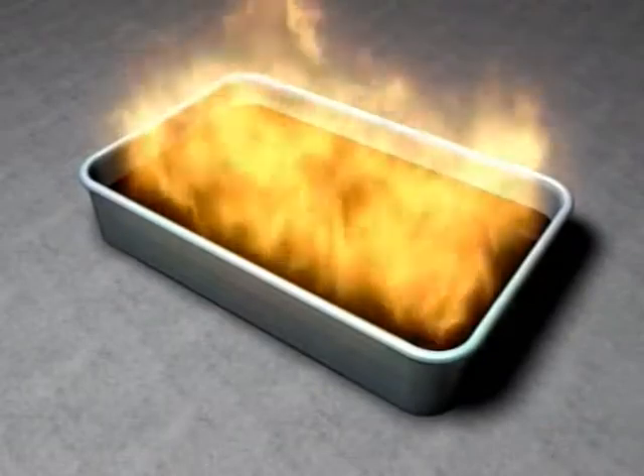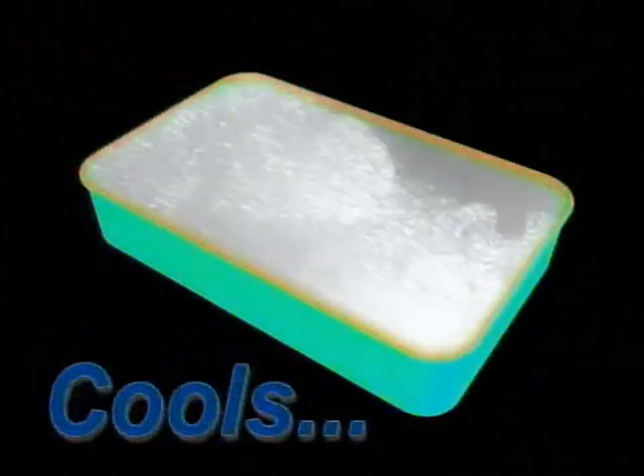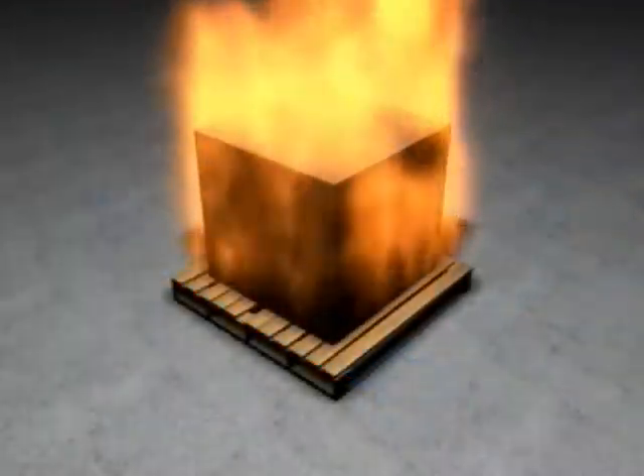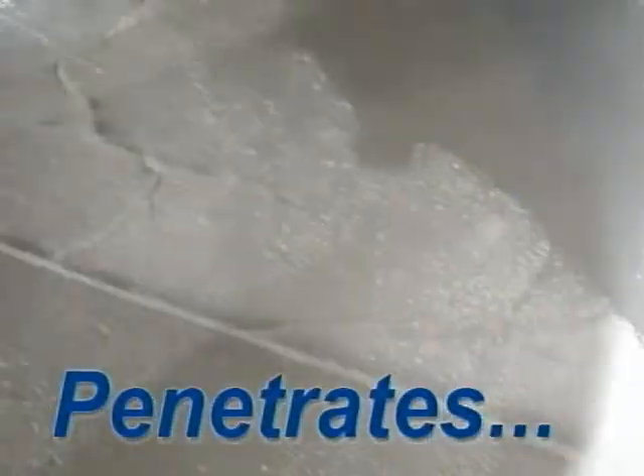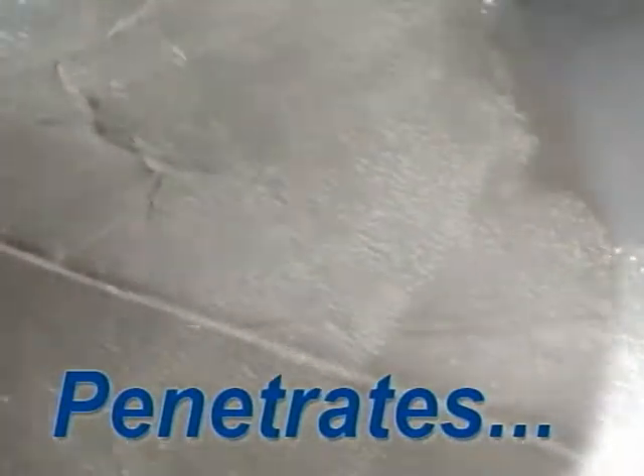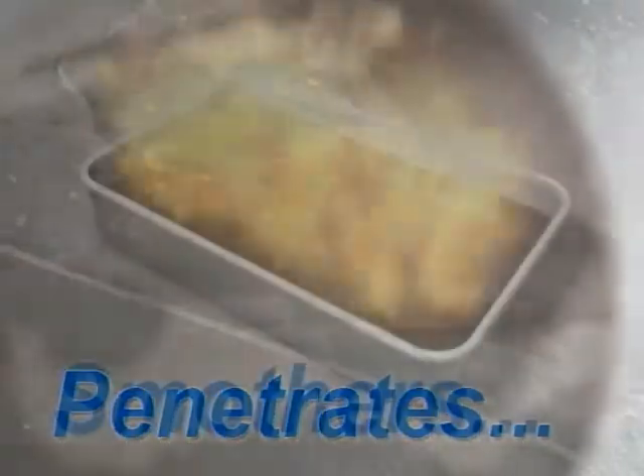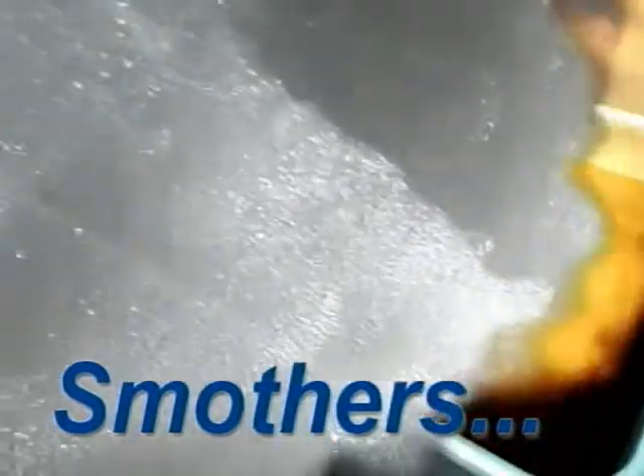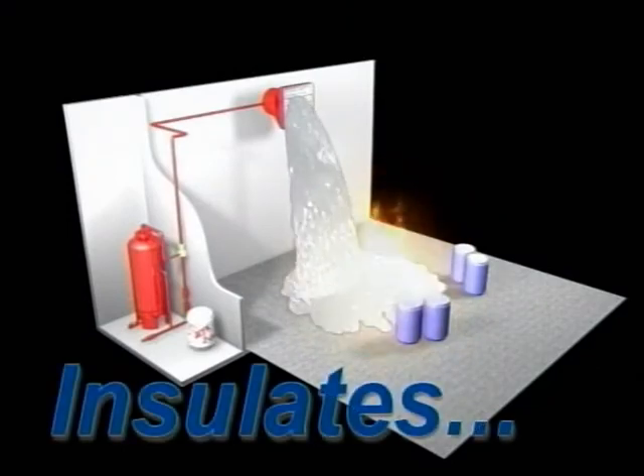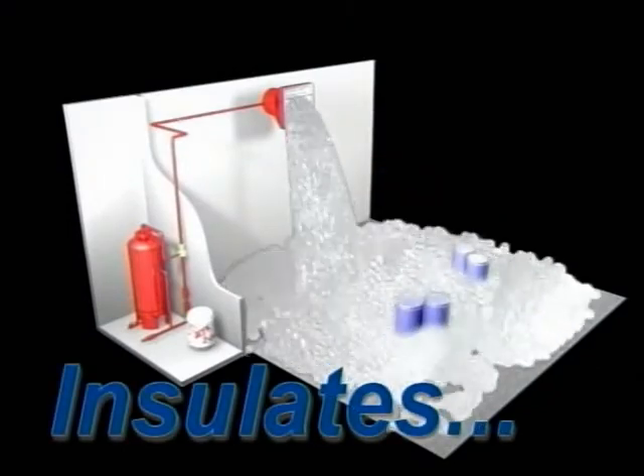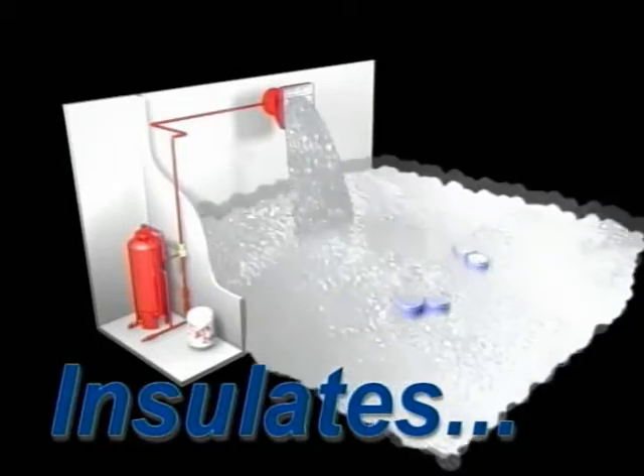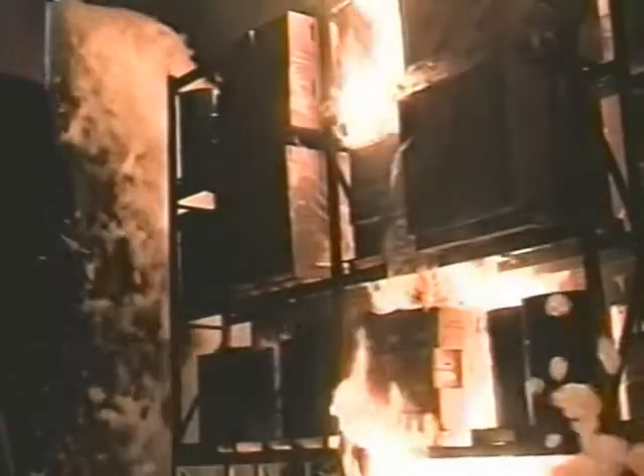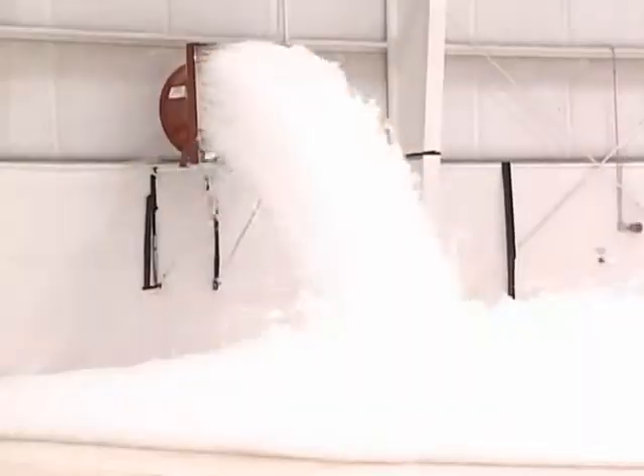It carries water to the fire, where it drains out of the foam and cools the fire, the hazard, and the surrounding area. The low surface tension of the draining solution penetrates Class A materials and reaches deep-seated fires. It smothers the fire by reducing the air supply to the fire. And finally, it provides an insulating barrier around exposed materials or structures to help prevent the fire from spreading. It does all of these things using substantially less water and foam concentrate.